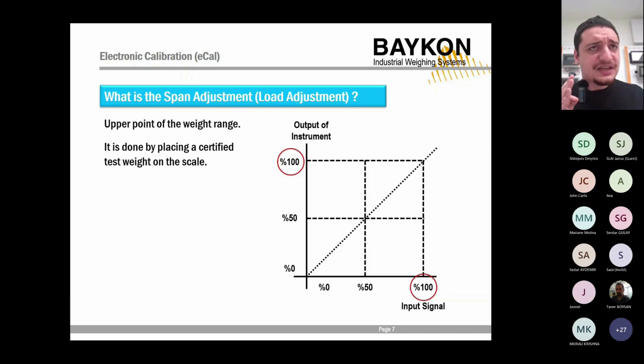In the worst case scenario, this is the absolute minimum weight that we can choose for the scale to be measuring for calibration purposes, 10%. And by the way, it is not always correct to choose 10% because, when the maximum capacity increases, we have a readability issue. So 10% might not be readable for the scale that we are using, but the minimum amount of weight that we will be using should be around 10%.